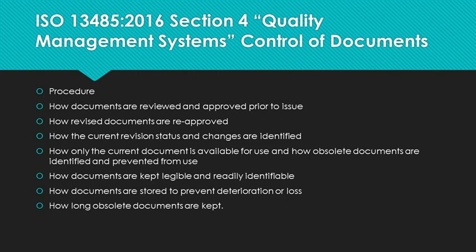Now, your company has to be careful with this one, as obsolete revisions of documents controlling the manufacturing process, think of work instructions, have to be kept for at least the life of the product and retained according to regulatory authority requirements. So if your regulatory authority says life of the product plus 2 years, you must implement that in your standard and your procedure.